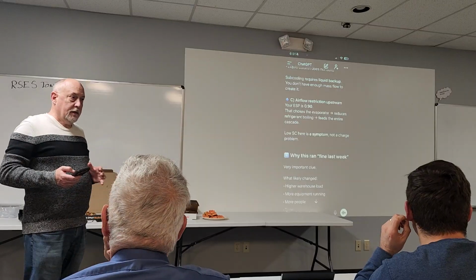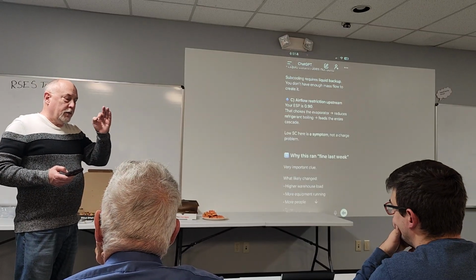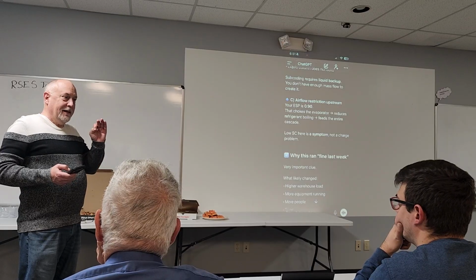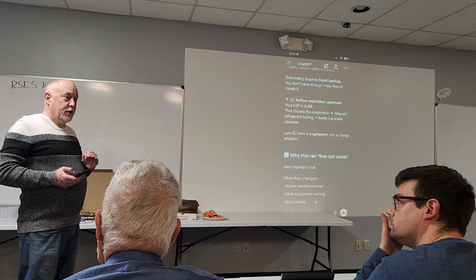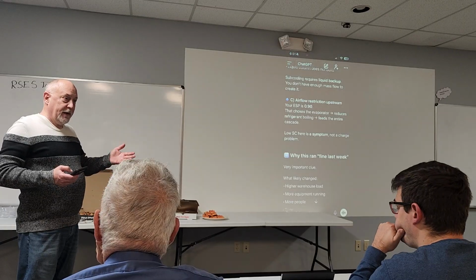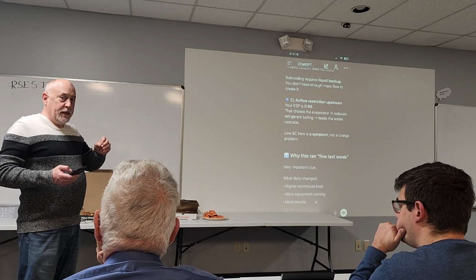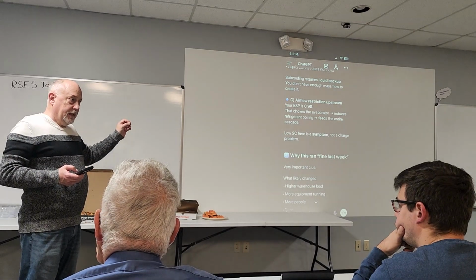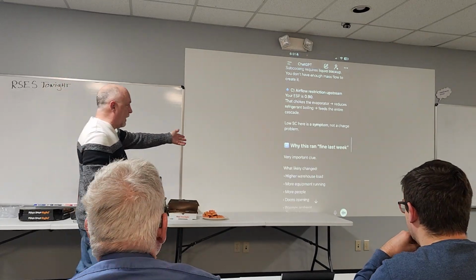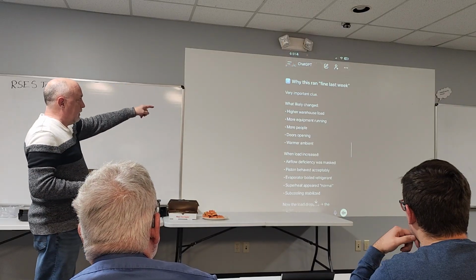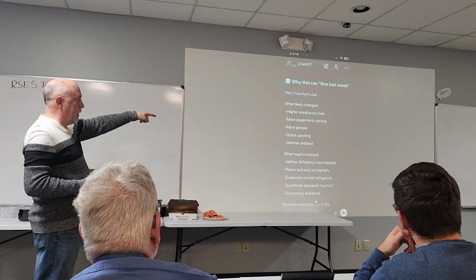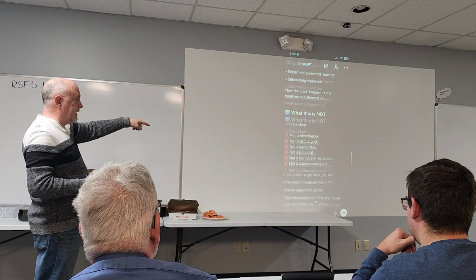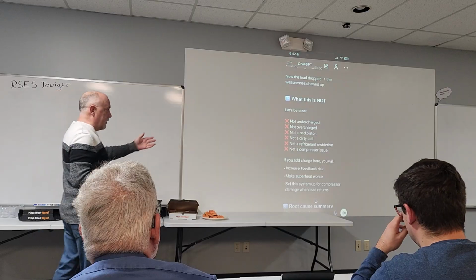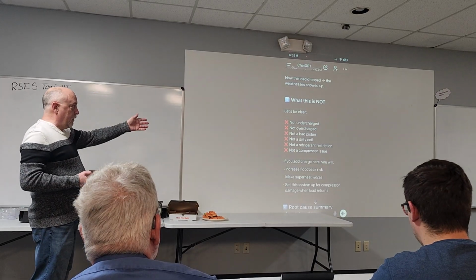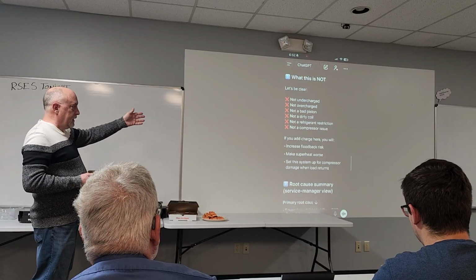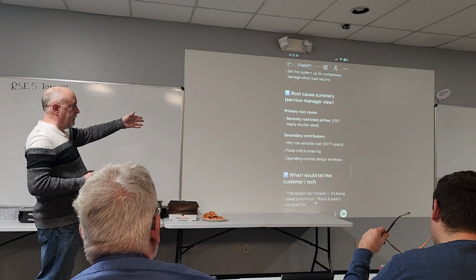Well, yeah, you're right, I'm just being devil's advocate here. If you'd walked out and said the condenser fan motor's operating at full speed and looks good, the more information you can give it, the better it's going to complete the problem. It's trying to predict what the problem is, why it ran last week, what likely changed. Maybe you had a higher load, maybe more people on there. What it's not is an undercharge, or an overcharge, or a bad piston, or a dirty coil, or a refrigerant side restriction, or a compressor issue. So it's nailing these things down pretty well off this information.